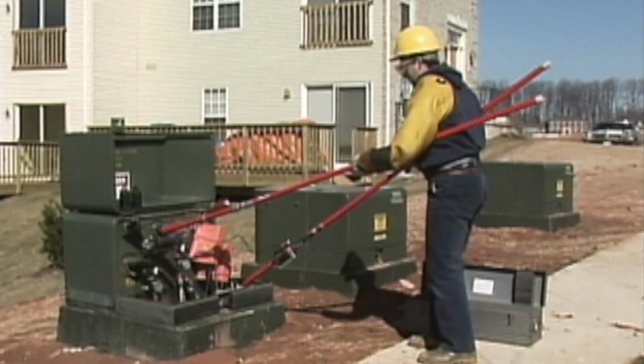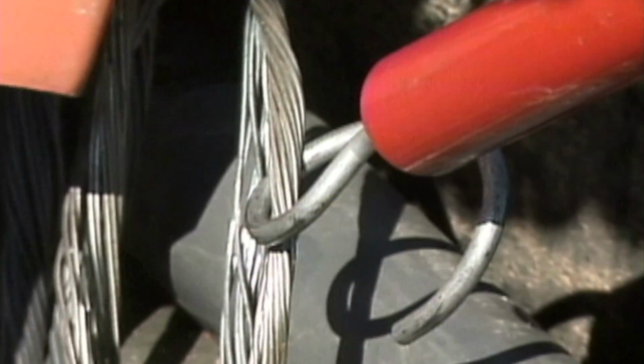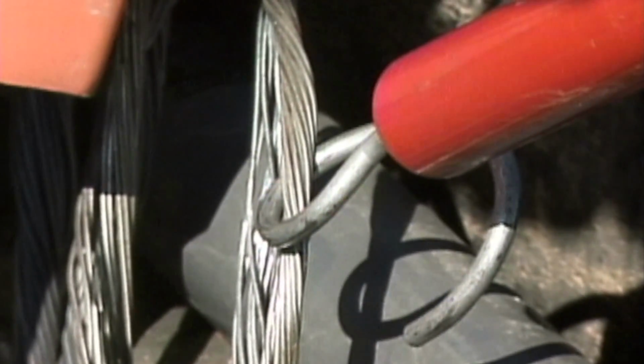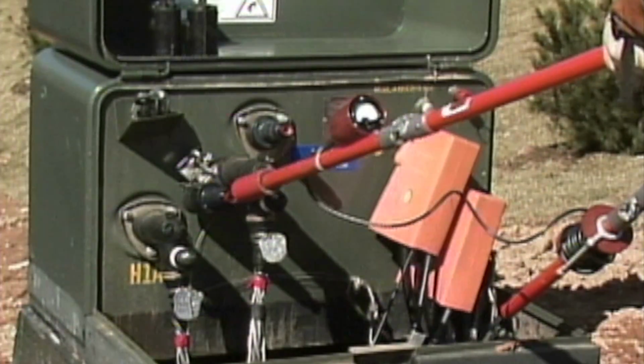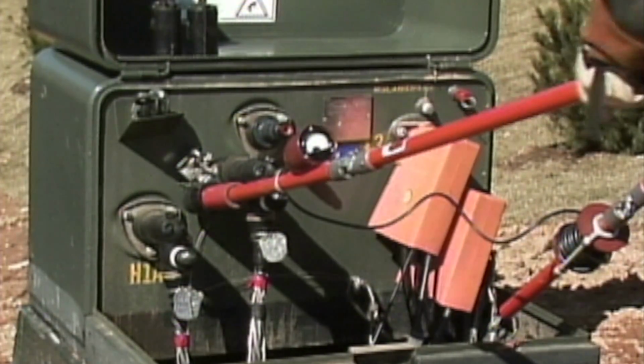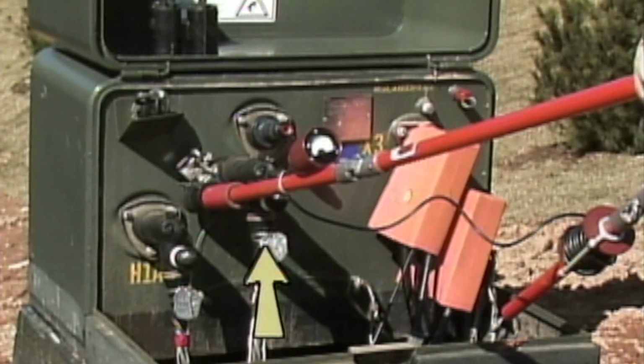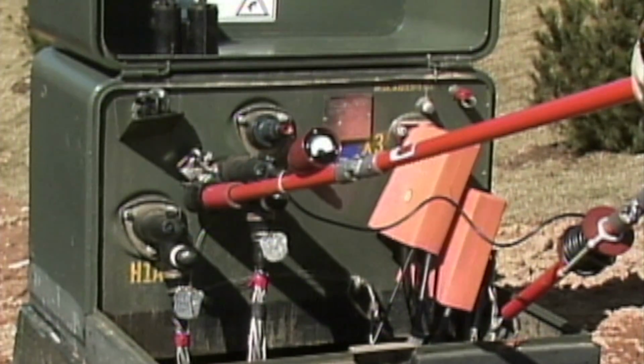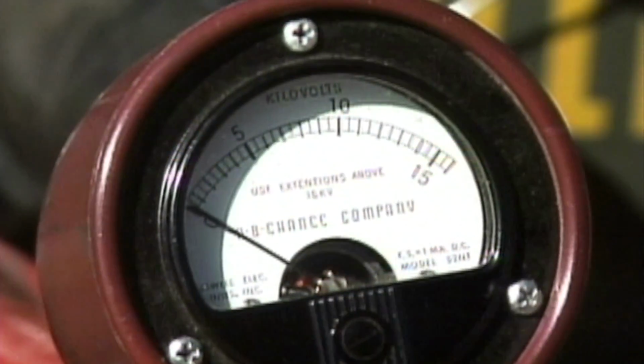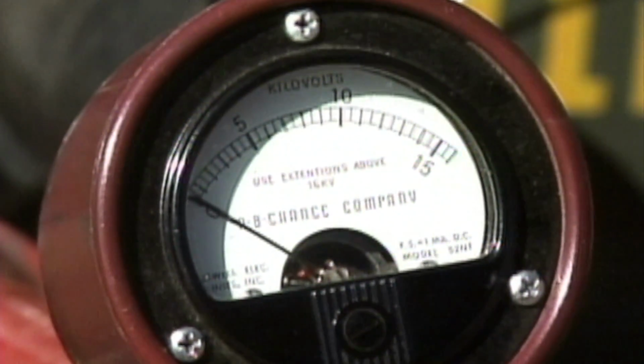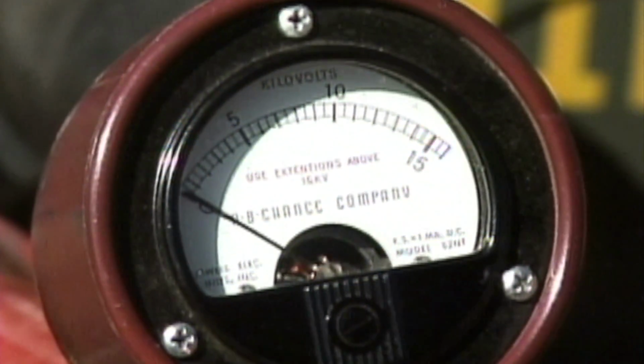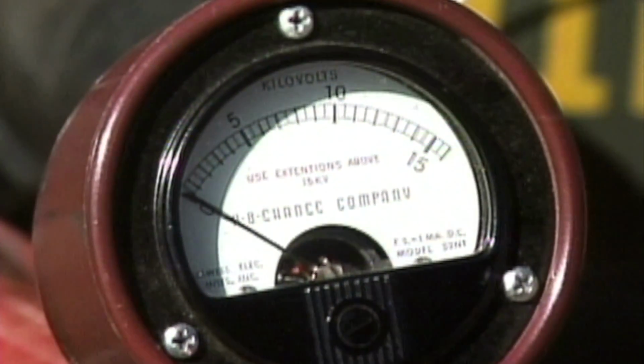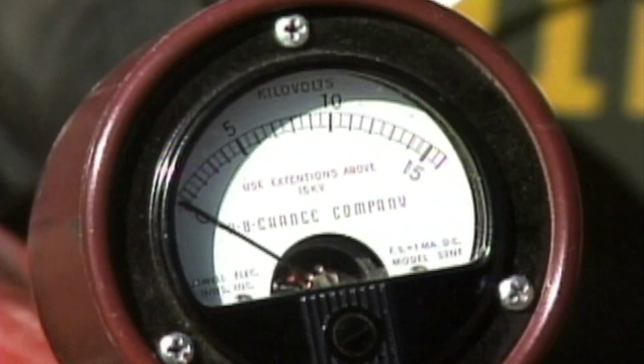Now he can test the cable for dead. He keeps one test probe on the transformer ground and places the other probe on the second position of the feed-through bushing. Since the other end of this cable has been disconnected from its energized source and then grounded, the cable should test dead. The reading between the feed-through bushing and ground shows 0 volts. This verifies that the cable is de-energized.